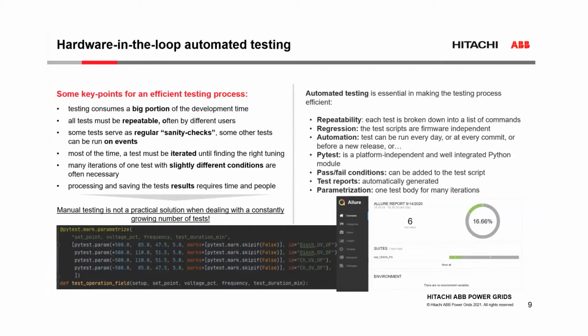Most of the time, a test has to be iterated, for example to find the right tuning for our controllers, but also because there are cases, like a fault ride-through capability test, where we have to test many different types of faults with different durations. We end up with a high number of iterations of tests with very similar conditions and always the same procedure.